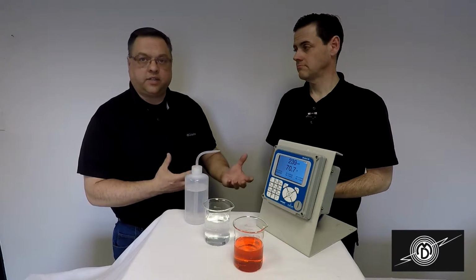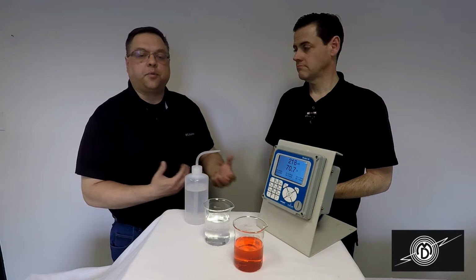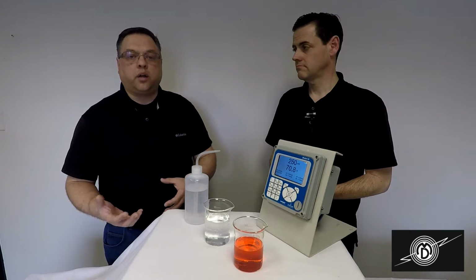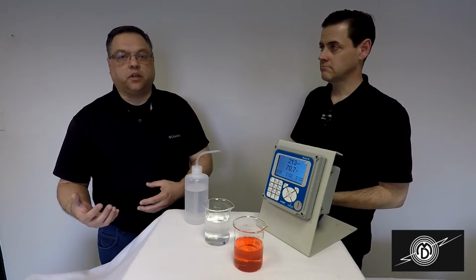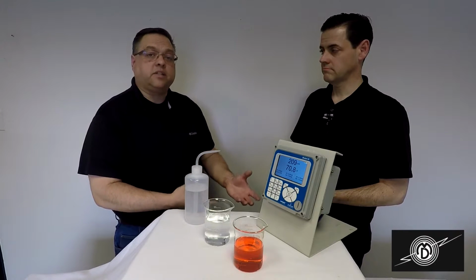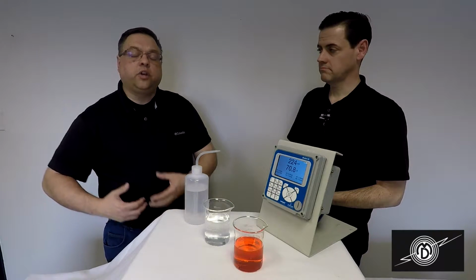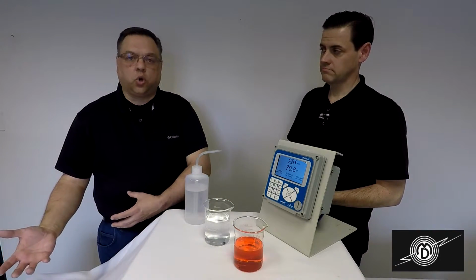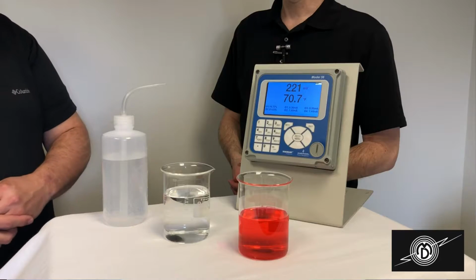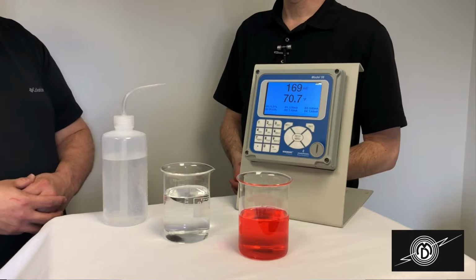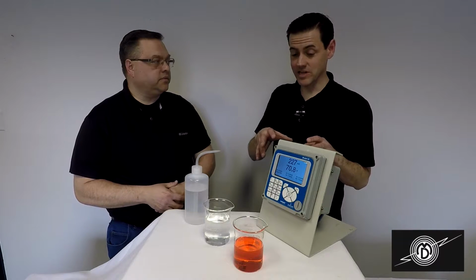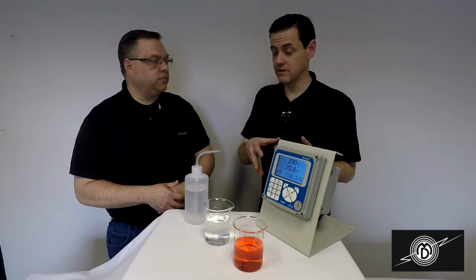ORP stands for oxidation or reduction. It's a type of reaction. An example of that is when you add chlorine to water, you are adding an oxidizing agent. That generates a millivolt signal. When you add sodium bisulfite to water, you can reduce the level of chlorine. That too gives off a millivolt signal that a sensor can pick up. So ORP is essentially a voltmeter for the water.